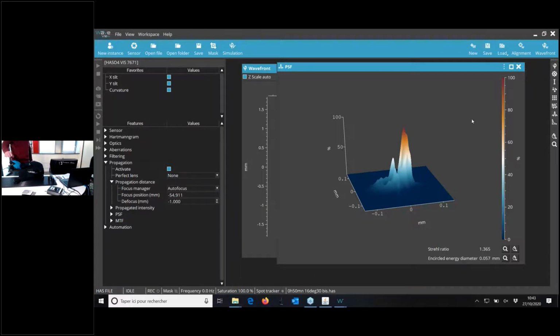The sensor is now set on the RFX2, which is set on the LA100, and we have a 100mm collimated beam available here. So if you put a flat mirror here, the beam is directed and measured by the Wavefront sensor. So like a Zygo, like a physical interferometer, you can measure large diameter optics in this part, except that you're not sensitive to vibration, you're not sensitive to air turbulence because you can just average.